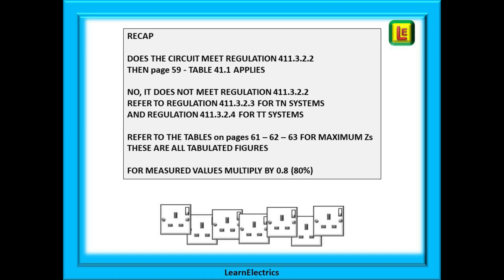A quick recap: does the circuit meet regulation 411.3.2.2? If it does, then page 59 table 41.1 applies. If not, refer to regulation 411.3.2.3 for TN systems or regulation 411.3.2.4 for TT systems. Then to find the maximum ZS for the circuit, refer to the tables on pages 61, 62, or 63. These tables all show tabulated figures. To find the measured values, multiply the numbers in these ZS tables by 0.8 — this is the 80% rule — and this is the ZS that you should measure with your test meter.